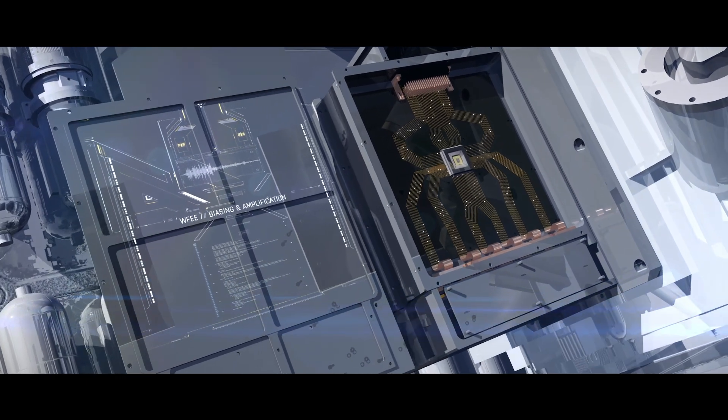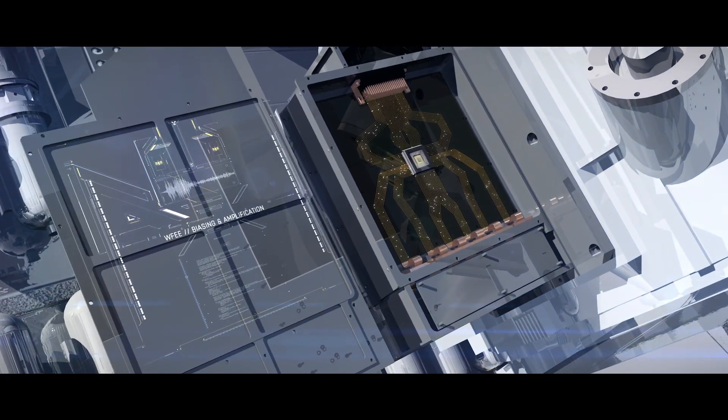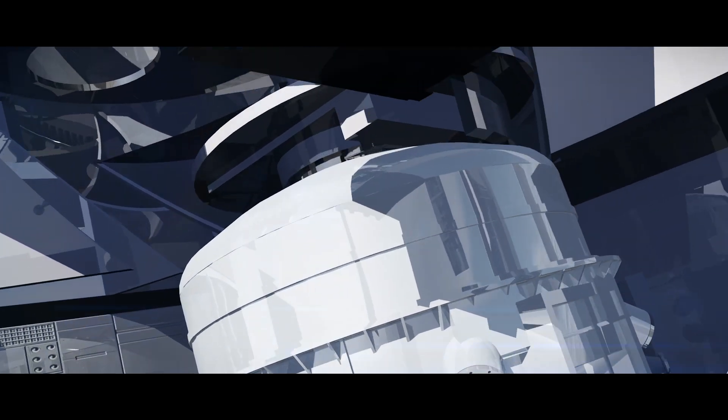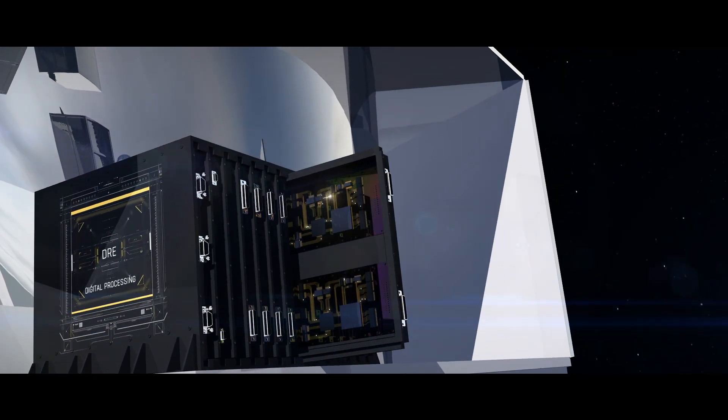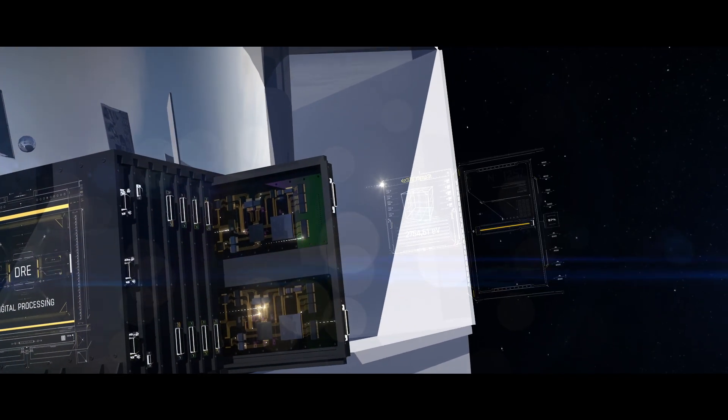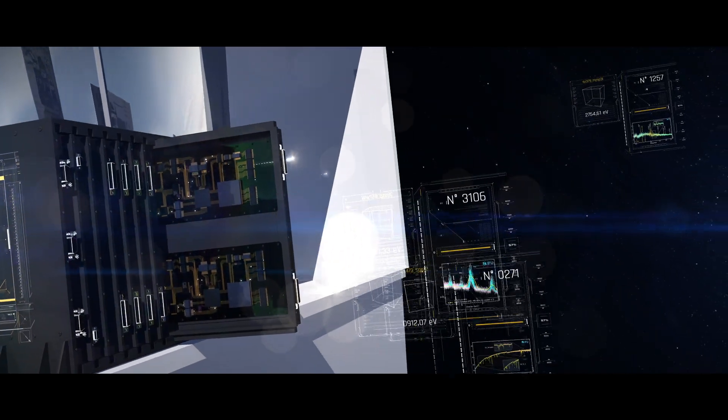Amplified with a very low level of noise, then digitized, these signals are individually analyzed to precisely estimate the energy of each X-ray photon.